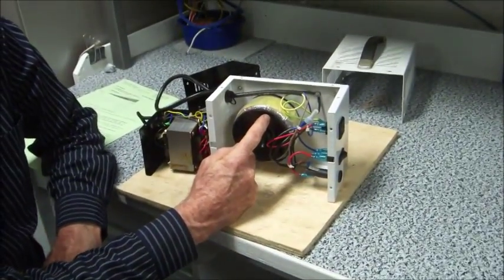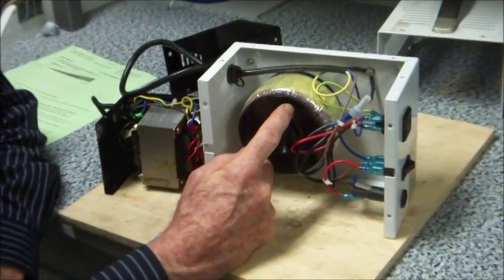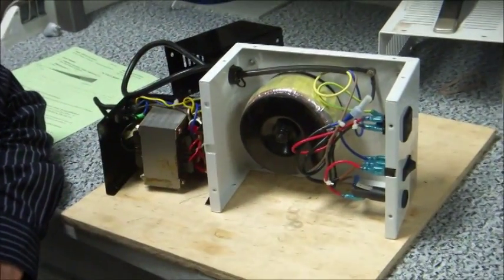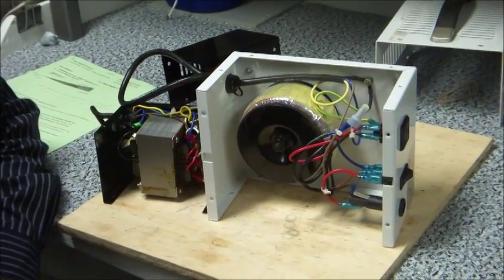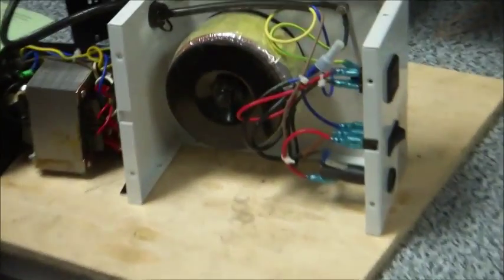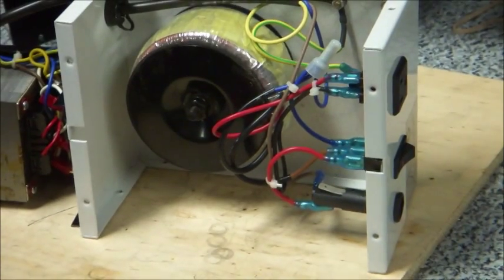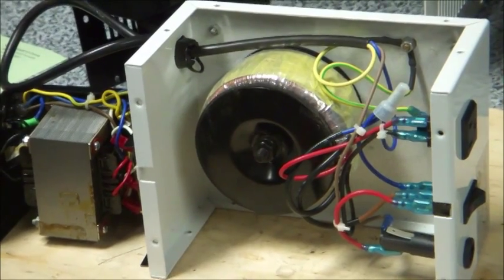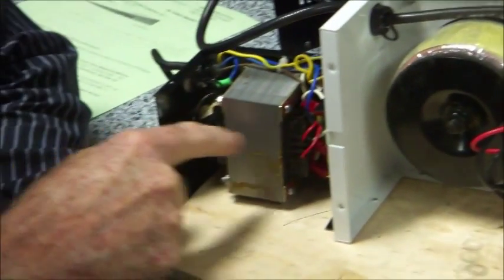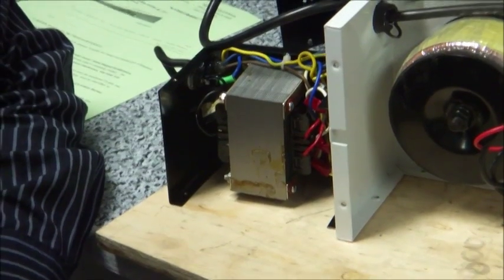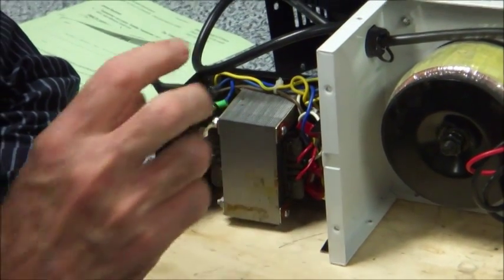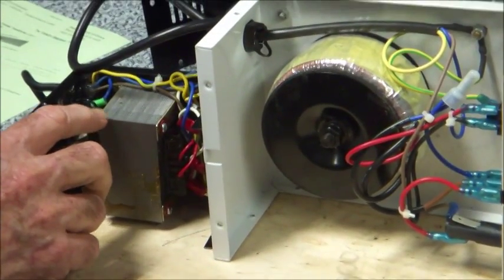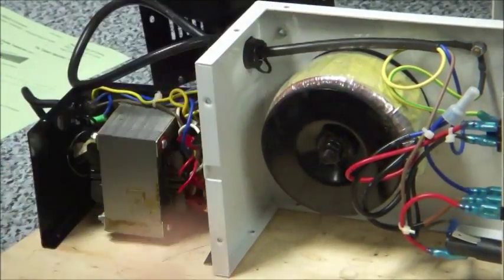Some of the features of the toroidal transformer compared to the EI transformer is that the toroidal transformer uses enamel wire, which is 180 degree insulation class. In other words, it can run at 180 degrees. It's also double coat. It's got a double layer of enamel. In the EI transformer, it only uses 105 degree insulation class or 130 degree insulation class wire and it's not as thermally capable as the toroidal transformer.